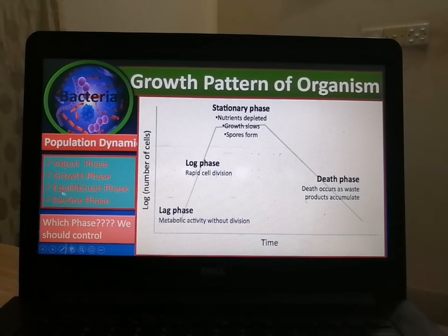So if you see, the equilibrium phase is the phase where all the biocide actually fails, because there is a total blanket, the biofouling is there, and a huge number of bacteria are always in the system. Now biocide is not working, but bacteria are at equilibrium phase, and they die and they grow, they die and they grow. After a certain point bacteria do not grow much, but the slime, the exhaust of the bacteria, the enzyme secretion of the bacteria has already damaged the system and created a very thick blanket that already fouls the system.